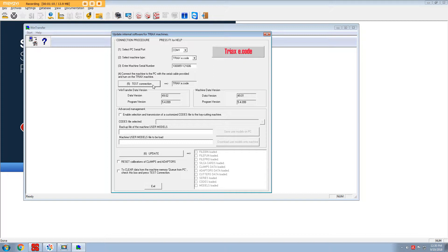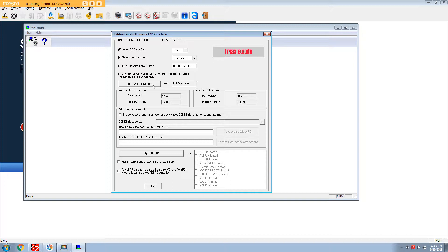So getting back to if you have a problem with testing connection and you don't get a response, don't worry too much. It is just a corrupt database. The machine will read 0.0.0 or 0.00. It probably won't have a program version or it might have one or the other. You go into your WinTransfer and press test connection and nothing happens. As long as you use a proper serial cable and a proper serial port on a PC, all you need to do is basically just press update and it will automatically do it.